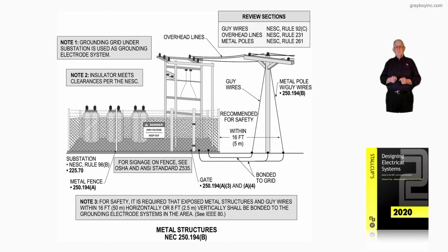Now, this illustration deals with metal structures in accordance with NEC 250.194B. Before we get into discussion here concerning this illustration, let's review the notes. Note 1 deals with the grounding grid under the substation, and it's used as a grounding electrode system, so to speak, for equal potential. Note 2, insulator meets clearances per National Electrical Safety Code.